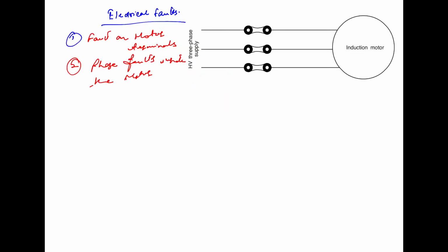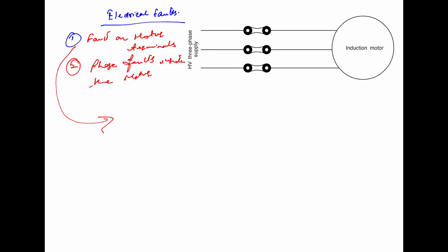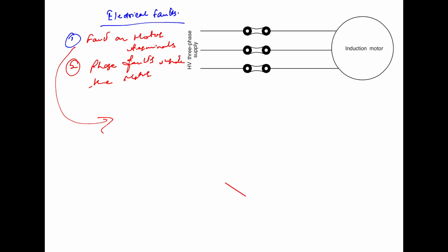Now let us discuss the electrical faults. First we discuss the fault on the motor terminals. The phase fault current at the terminals of the motor is considerably larger than any normal current, such as the starting current or any internal fault. So a high set instantaneous overcurrent relay is recommended for fast, reliable and inexpensive protection. So for the fault on the motor terminals, a high set instantaneous overcurrent relay is recommended.